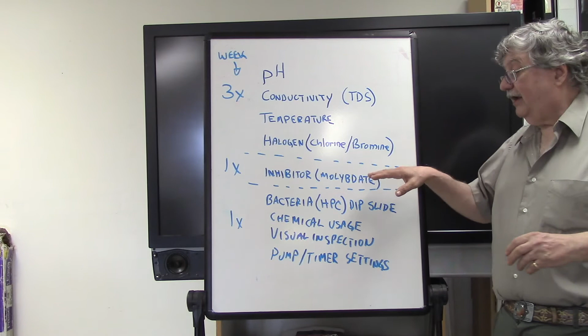Also, some consultants ask you not only to measure the halogen level 3 times a week, but also the corrosion inhibitor being used, often molybdate, occasionally something else. Depending on what your consultant put in the book, you might test for that molybdate inhibitor occasionally, once a week, or 3 times a week along with the others.